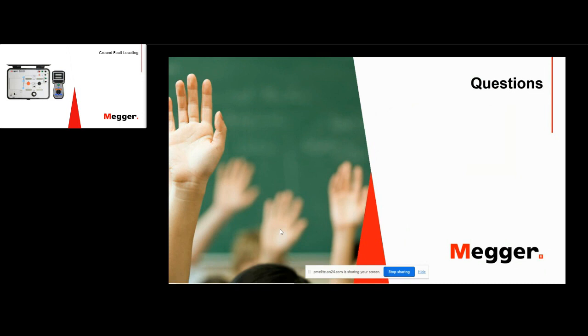An IT ungrounded AC system is isolated at the source and Terra at the load, so it has a stake at the load. These types of systems are used on critical applications, and they will not trip a breaker with a fault. But you do need to locate that fault, and that can be done as well. As far as the motors go, if they're on an ungrounded system or a high impedance ground, yes, you can actually find them.